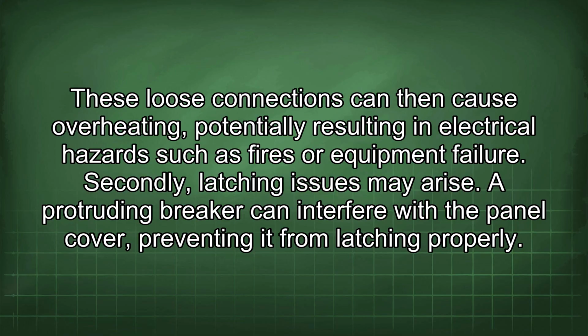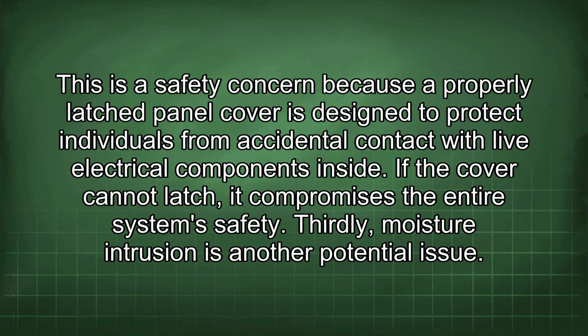Secondly, latching issues may arise. A protruding breaker can interfere with the panel cover, preventing it from latching properly. This is a safety concern because a properly latched panel cover is designed to protect individuals from accidental contact with live electrical components inside. If the cover cannot latch, it compromises the entire system's safety.